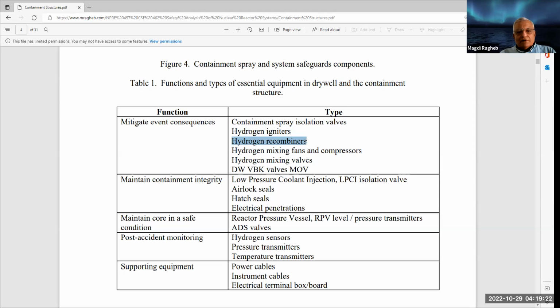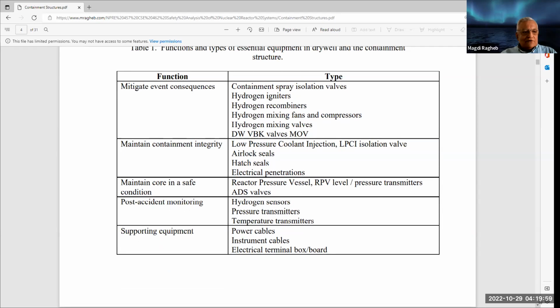Those recombiners caused our nuclear power plant here at Clinton to be delayed for a whole year of construction when they had to add those hydrogen recombiners, and it delayed the construction for a whole year. You have hydrogen mixing fans and compressors, hydrogen mixing valves, and so on. And unfortunately, as I mentioned, at the Fukushima accident, the pressure in the containment was so large that those valves that would release the hydrogen to the atmosphere could not function. The springs did not overcome the pressure in the containment. When we study the Fukushima accident, we'll bring that into attention.